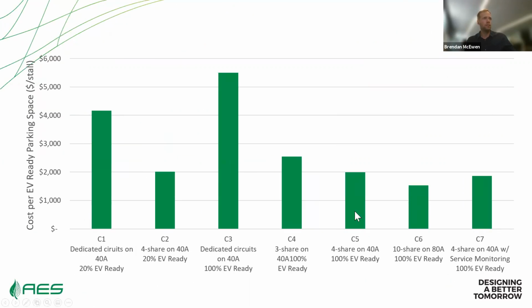For mid-rise, there are ways of doing 100% EV-ready ranging between about $1,500 and $2,000 per EV-ready space. For this scenario, the lowest cost strategy is sharing 10 parking spaces on 80 amp circuits, which was around $1,500 a parking space.